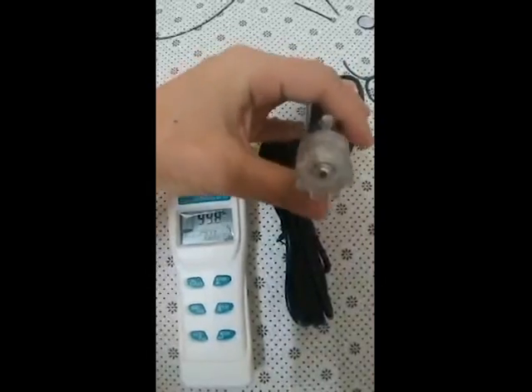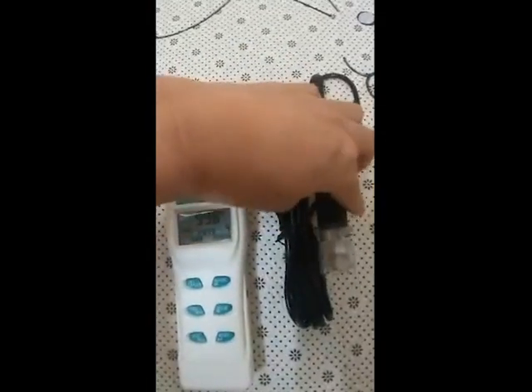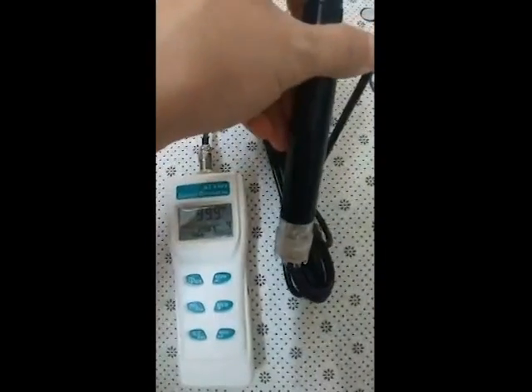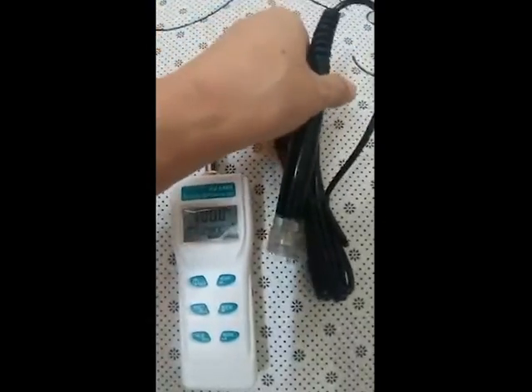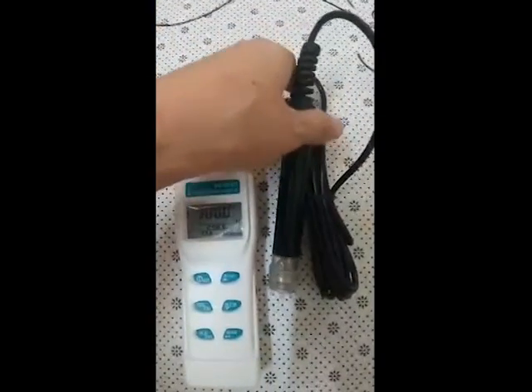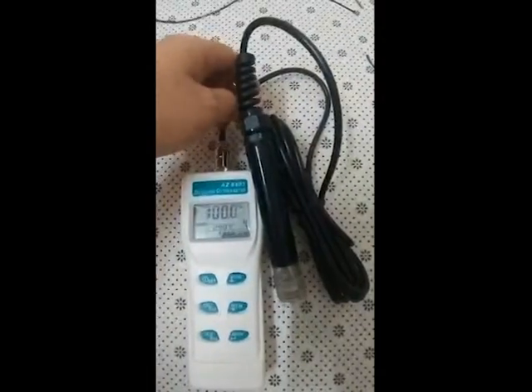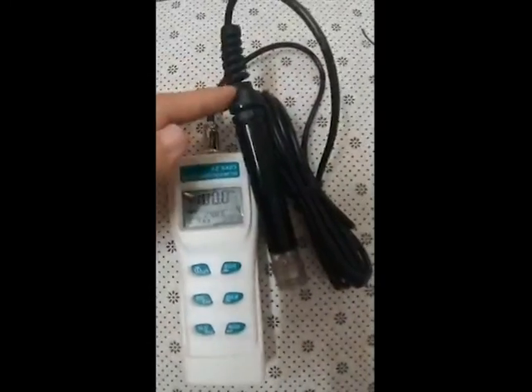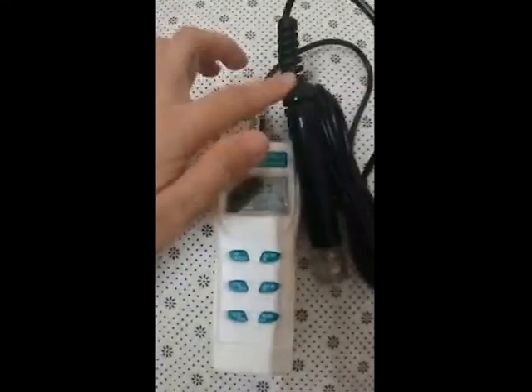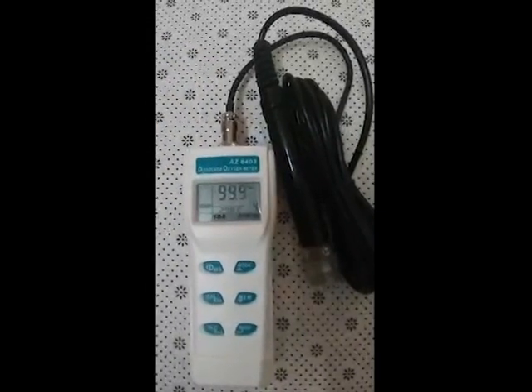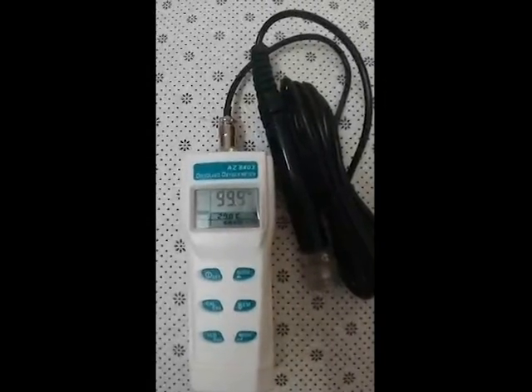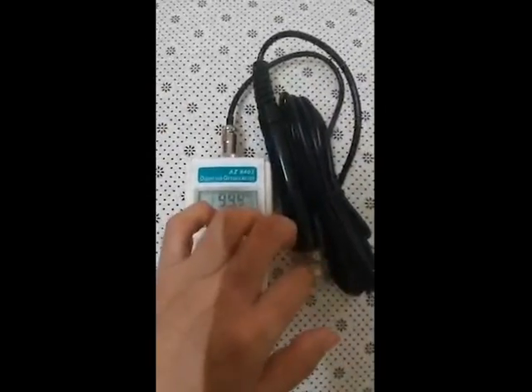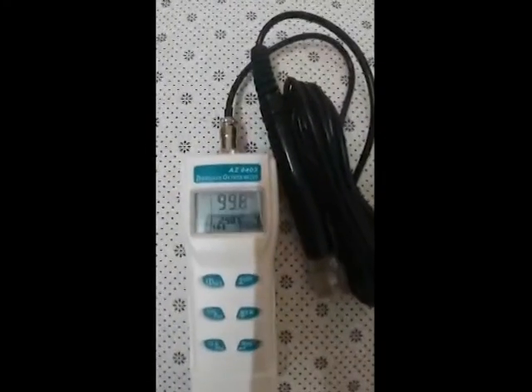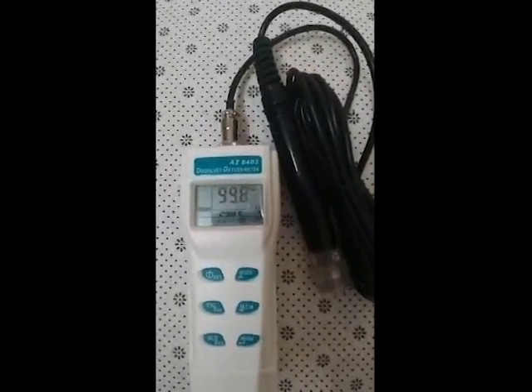The only thing you need to pay attention to, if you are testing in a container, is to make sure the membrane is under good protection. There should be no sharp device when you attach the membrane into the solution. Pay attention to the application temperature and humidity of the system. Also, if you want to soak this one in wild conditions, make sure this one does not drop into the bottom of the water resource like the lake or the river, to prevent mud from contaminating the surface of the membrane. This is all about the hardware.